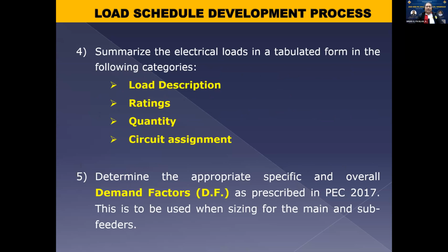So then for feeder sizing, we need now to determine the overall demand factor to complete the design process, for sizing the main and sub feeders. Okay, as prescribed in PEC 2017. So ito yung development process talaga ng isang load schedule. Kung hindi tayo copy-paste engineer. Kasi si copy-paste engineer, madali lang 'yan.